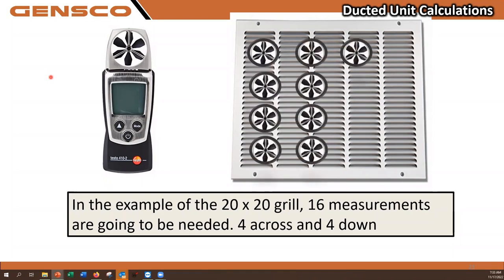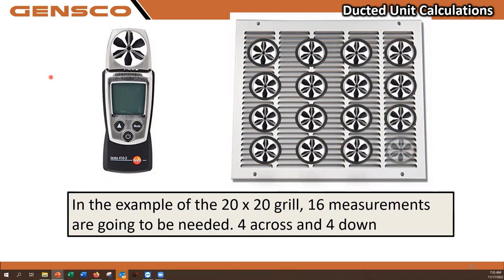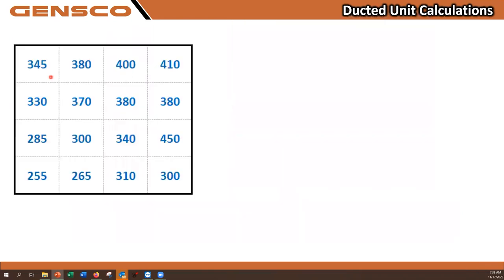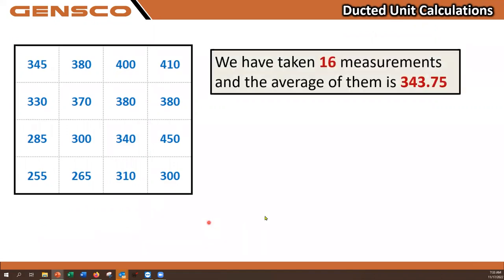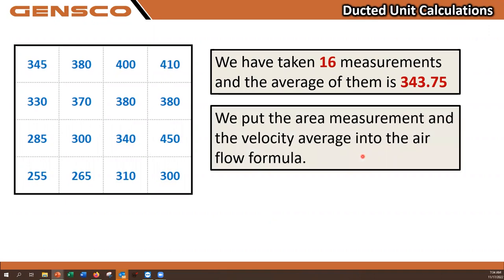I'm going to stick my velometer on the grill, wait for it to steady, and record the numbers. Something like this. Once I've done that, these numbers are going to go in a formula. These are my average velocities in feet per minute at the 16 different points of the grill that I've measured. The average of the 16 points is 343.75 feet per minute. I already know the area of my grill, so I'm going to put this into the airflow formula.